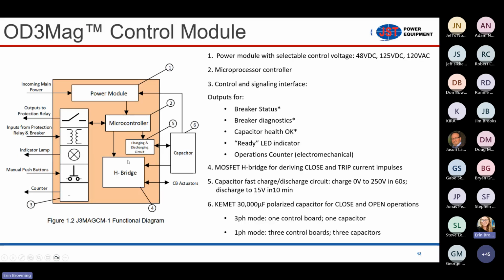The control board itself, this is a simple block diagram. Basically, it consists of a power module that's flexible with the type of control voltage, whether it's 48 volts, 125 volt DC, or 120 AC. There's a controller on board, and then there's a capacitor that's responsible for energizing the actuators.